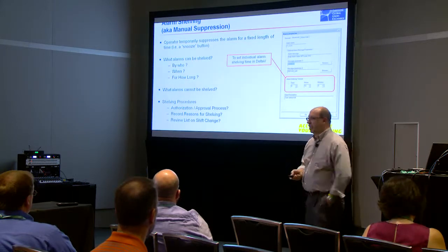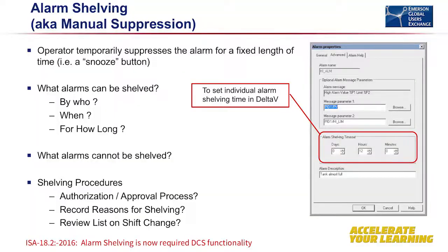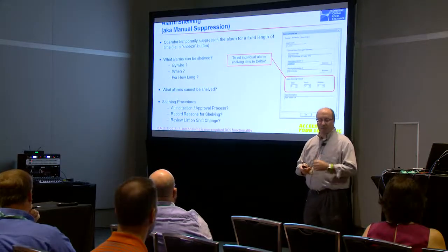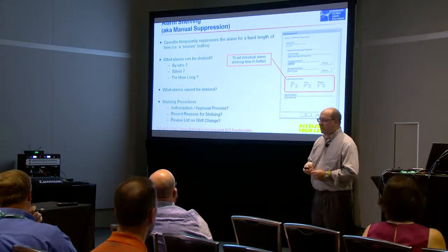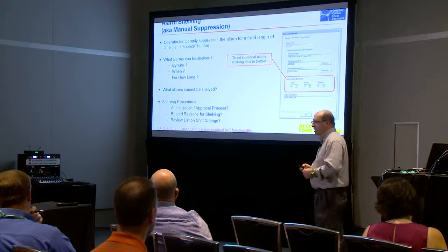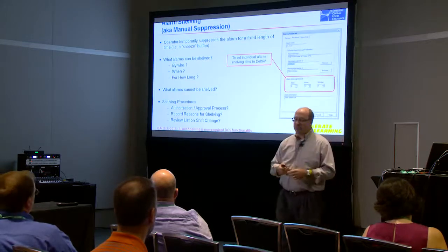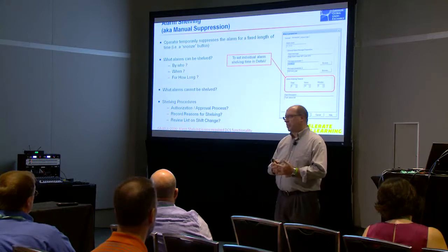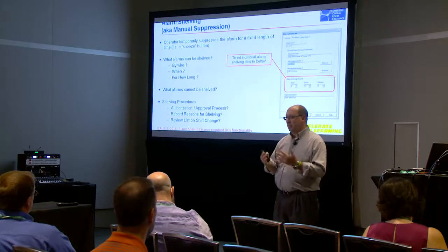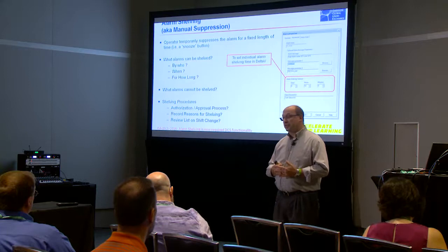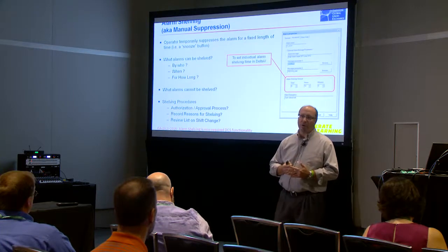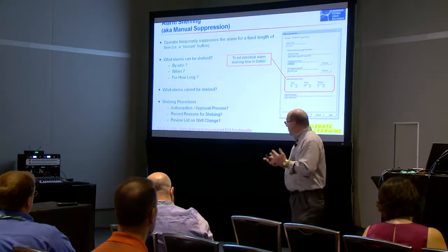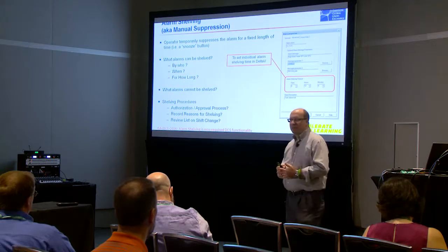Now, this is a native capability of DeltaV. Each alarm has the ability to have a different suppression timeout defined. So you can define how long the alarm could be shelved, whether it could be zero, which means it's not suppressible, or one shift or whatever. But the idea is you can think about under what circumstances operators can shelve alarms. Maybe only for the warning and advisory alarms, but maybe not critical priority alarms. So this is a really important and powerful capability.